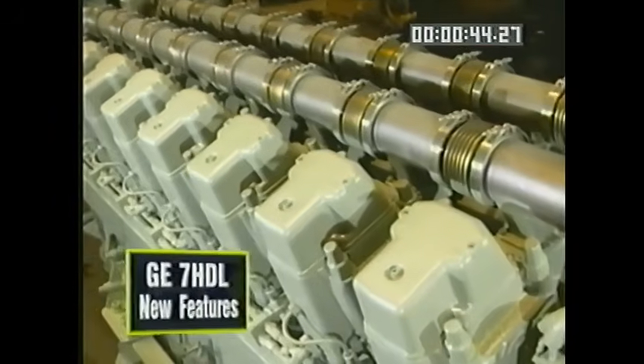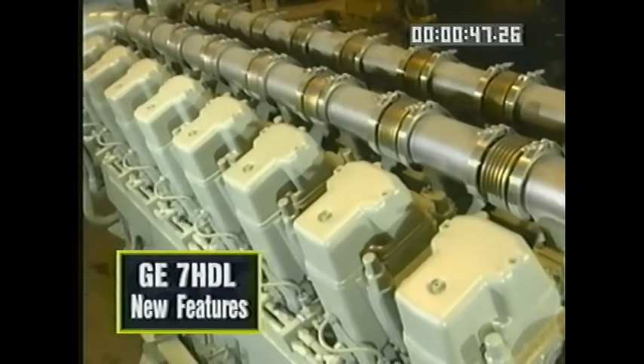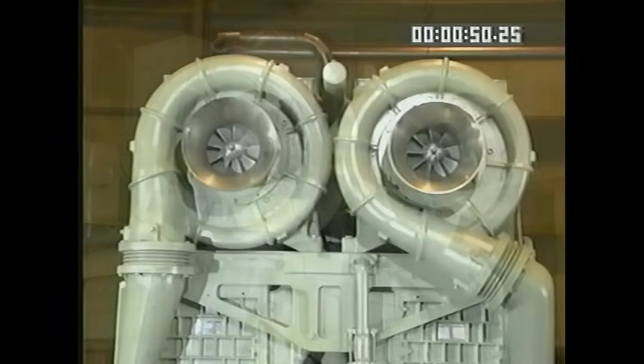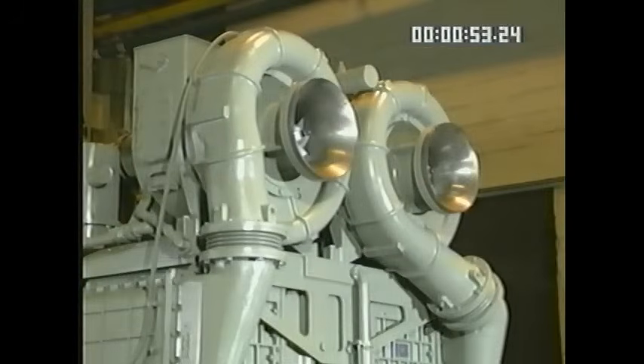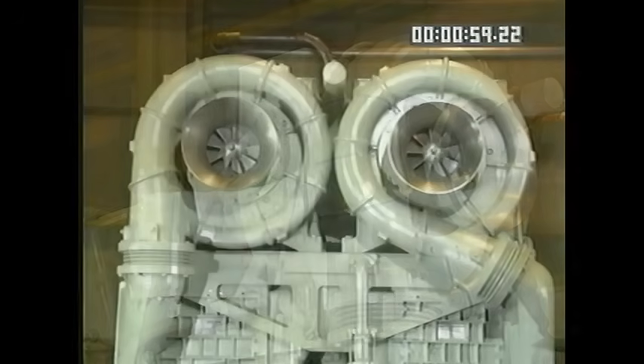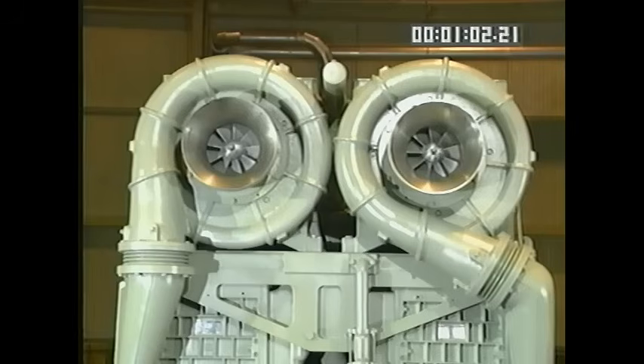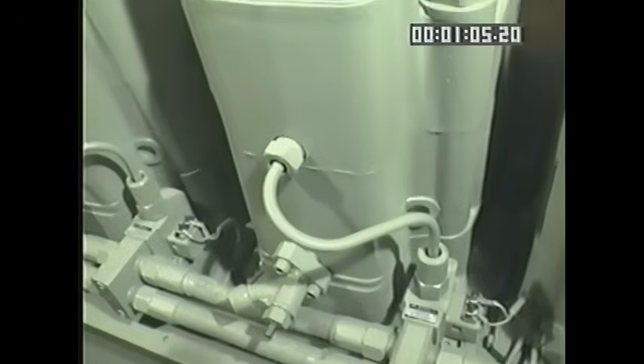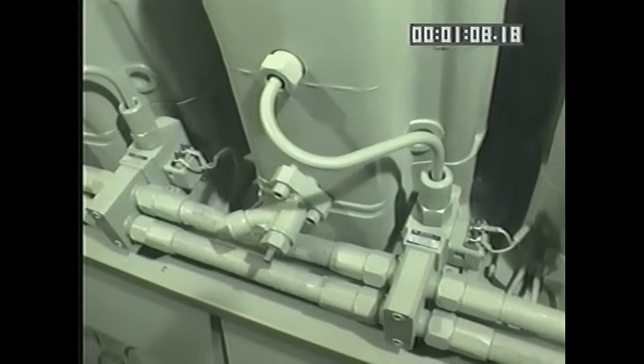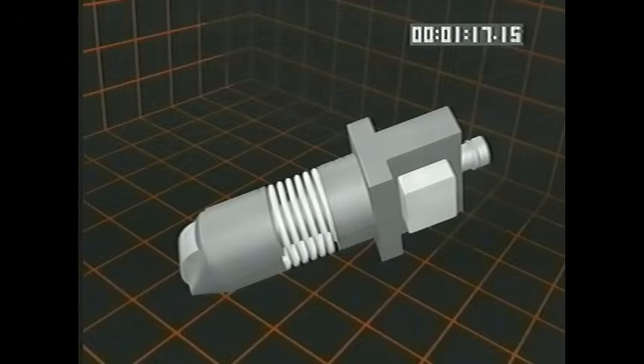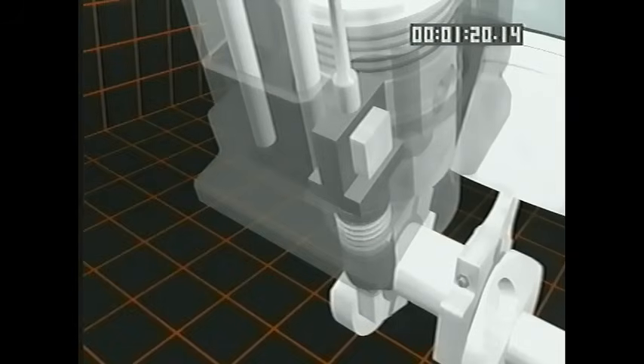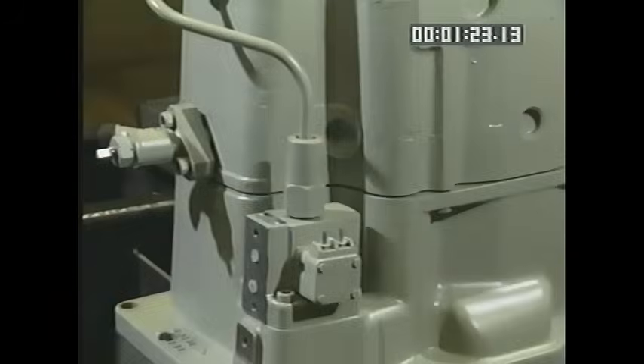Let's take a look at some of the new features found on the 7HDL. There are now 2 turbochargers. These twin turbos, designed and built by GE, include all of the latest features, including backward curved compressor vanes for optimum efficiency. Fuel is delivered through an electronic fuel injection system, resulting in the highest fuel efficiency and the lowest emissions possible. The individual fuel pumps operate without push rods. This allows a stiffer system and decreased combustion variability from cylinder to cylinder.